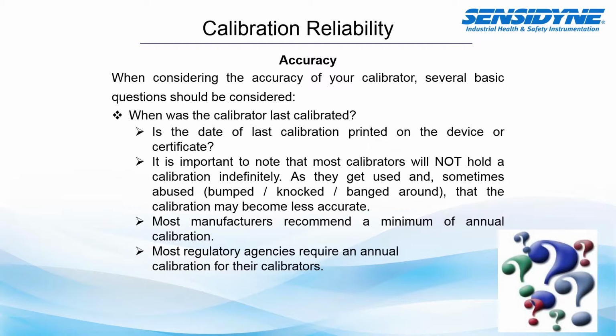Some additional questions that need to be considered would be, when was the calibrator last calibrated? Is the date of the last calibration printed on the device or on the certificate? Now, this is an important aspect because calibrators get brought out in the field, they get bumped, and they may actually have slight deviations to them. Over time, drift can occur within your calibration device.